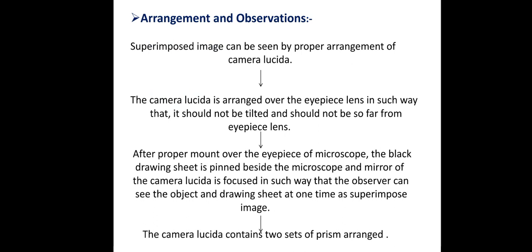Regarding arrangement and observation: a superimposed image can be seen by the proper arrangement of the Camera Lucida. The Camera Lucida is attached over the eyepiece lens in such a way that it should not be tilted and should not be too far from the eyepiece lens. After proper mounting over the eyepiece, the black drawing sheet is placed beside the microscope and mirror of the Camera Lucida. It is focused so that the observer can see the object and drawing sheet at one time as a superimposed image.